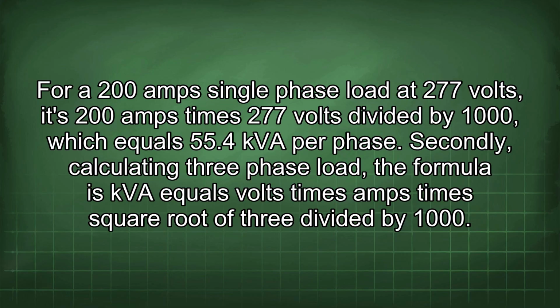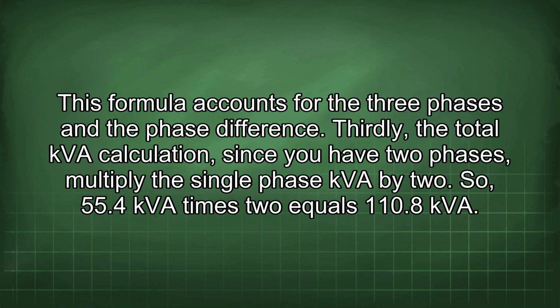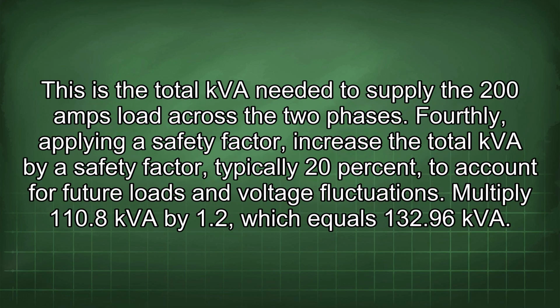Secondly, calculating three-phase load. The formula is kVA equals volts times amps times square root of 3 divided by 1000. This formula accounts for the three phases and the phase difference. Thirdly, the total kVA calculation. Since you have two phases, multiply the single phase kVA by 2. So 55.4 kVA times 2 equals 110.8 kVA. This is the total kVA needed to supply the 200 amps load across the two phases.